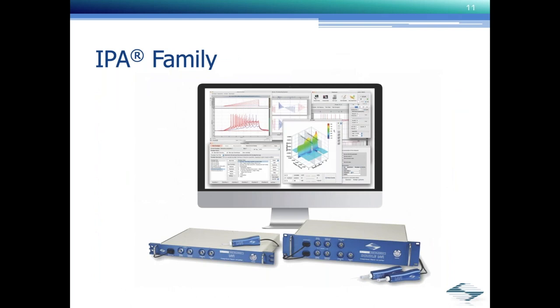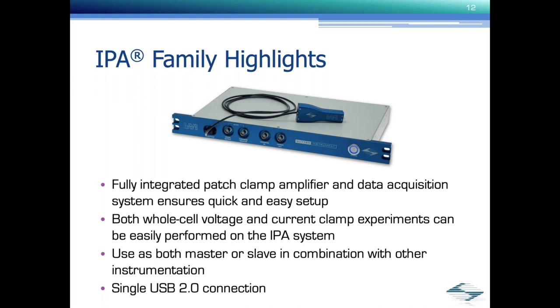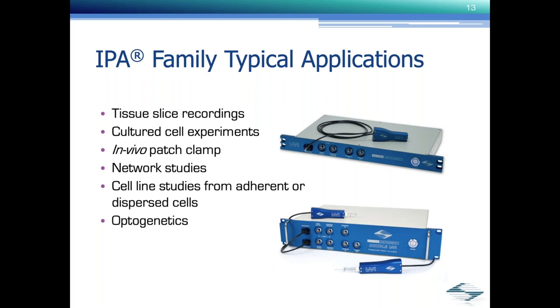We introduced the IPA and the Sutter patch software in the fall of 2015. A year later, it was followed by the double IPA. All of the IPA family members share the same specifications, which is fully integrated patch clamp amplifier and data acquisition system for quick and easy setup. They support both whole cell voltage and current clamp experiments. They support master-slave combination with other instrumentation, and they use a single USB connection. One thing that many people are not aware of is that multiple IPA amplifiers can be connected and are fully supported in the Sutter patch software to provide additional fully synchronized channels. They can be used in a broad range of whole cell and current clamp applications.